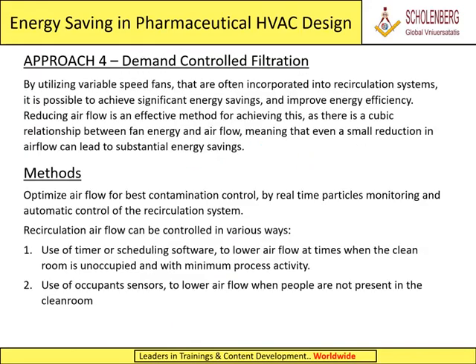Approach 4. Demand-controlled filtration. By utilizing variable speed fans, that are often incorporated into recirculation systems, it is possible to achieve significant energy savings, and improve energy efficiency. Reducing airflow is an effective method for achieving this, as there is a cubic relationship between fan energy and airflow, meaning that even a small reduction in airflow can lead to substantial energy savings.